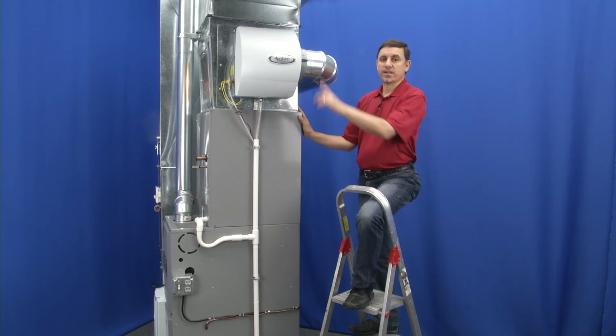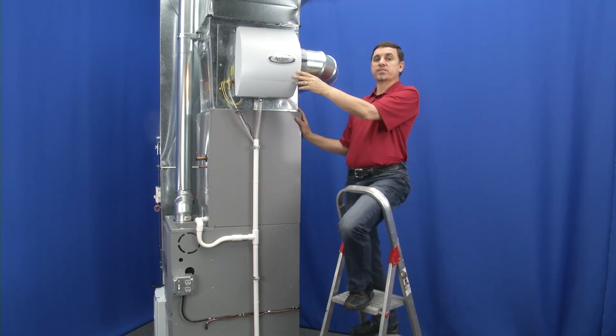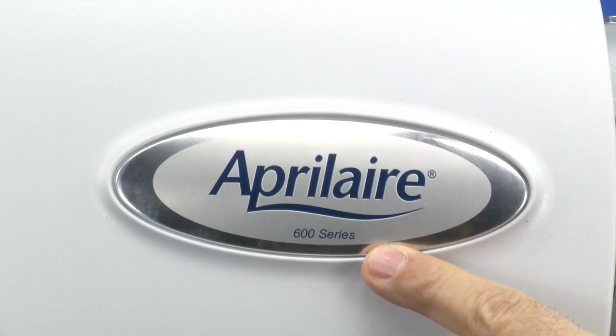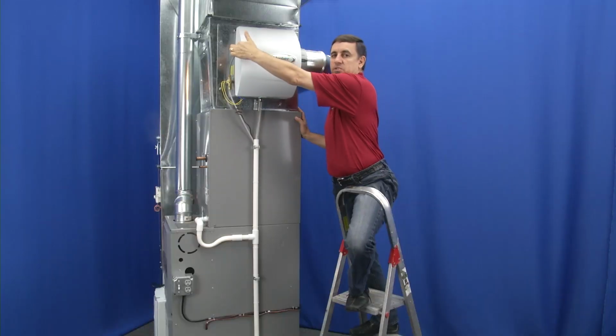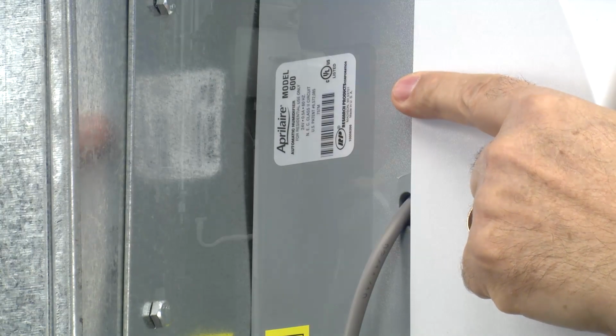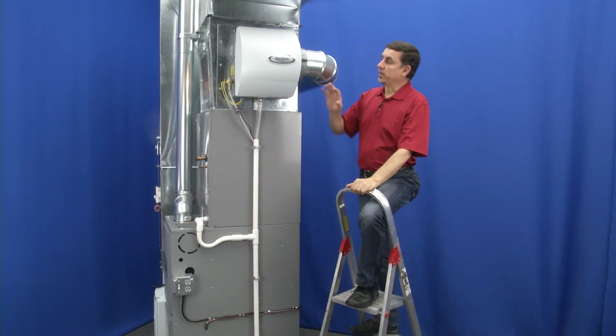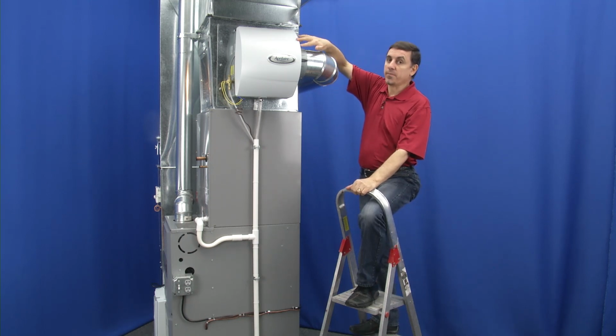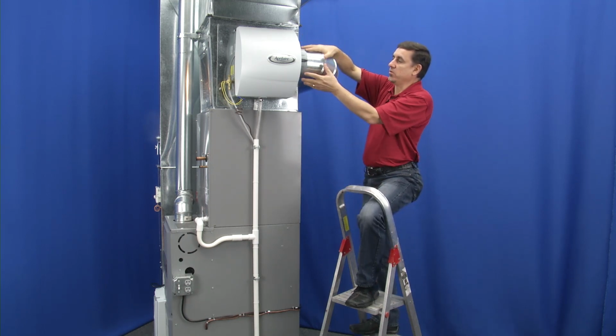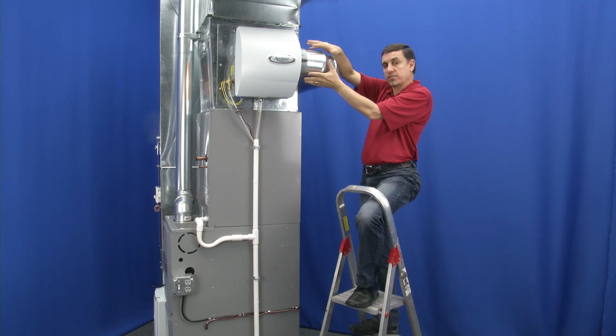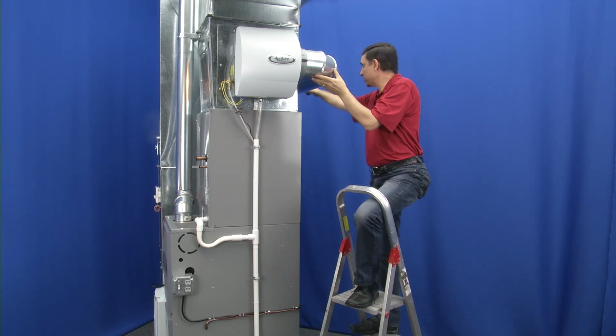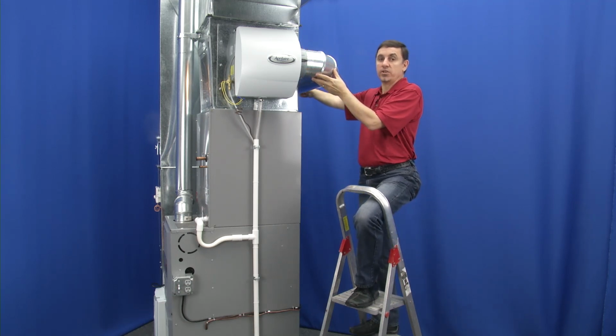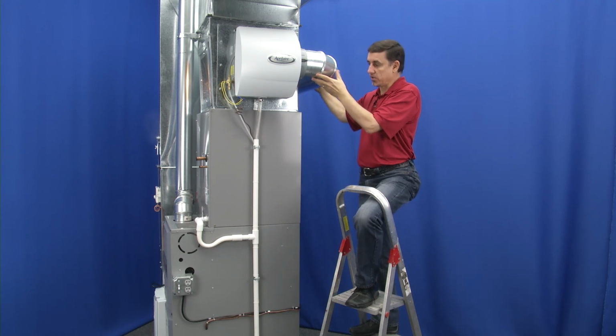Our demo unit has this humidifier. This is a model 600 AprilAire mounted to the side of it. You'll see there's a model number here, and there's also a sticker over here on the side that gives you the model and serial number. This one being a 600, it's a bypass style humidifier. So there's a 6-inch round bypass duct that's attached here, and it comes around and is attached to the return air ductwork, which we discussed earlier.